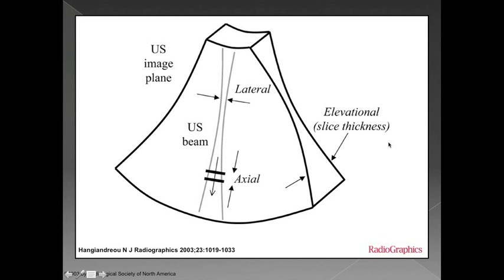And then your elevational or your slice thickness is pretty much fixed. We talked about focus on the last slide, we were actually talking about focus just in the two dimensions that are the image. But if we think about the third dimension, which is the slice thickness, most of our transducers right now actually have a fixed focal zone. And so the slice thickness is actually going to change depending on the depth of the image that you're looking at.